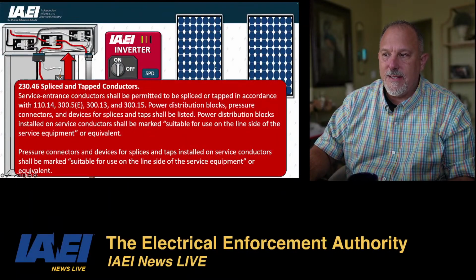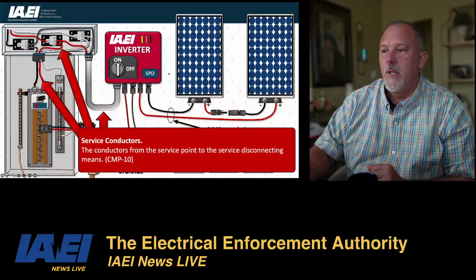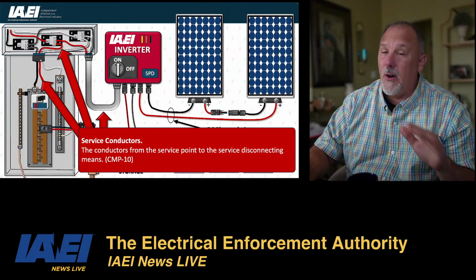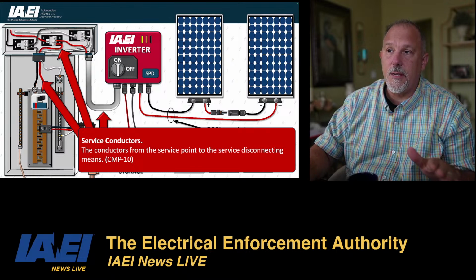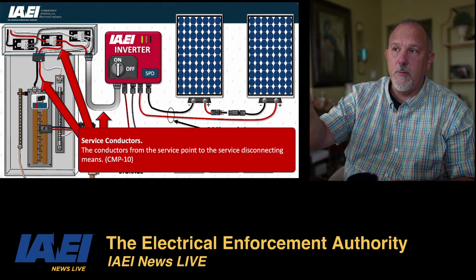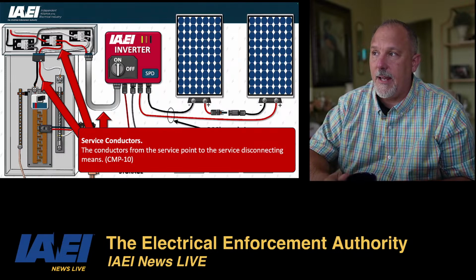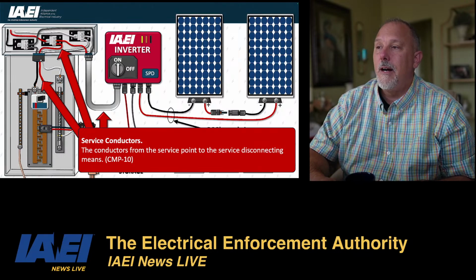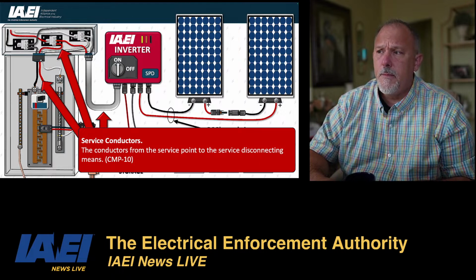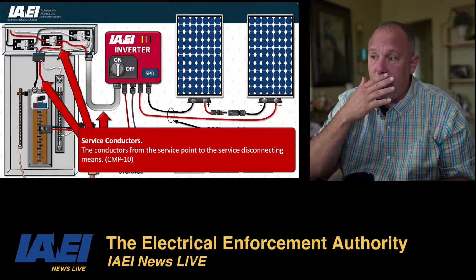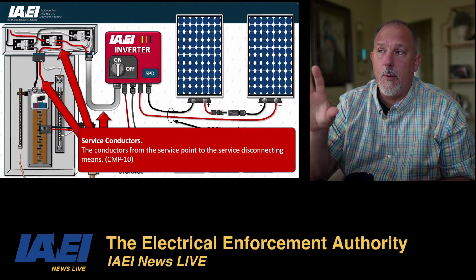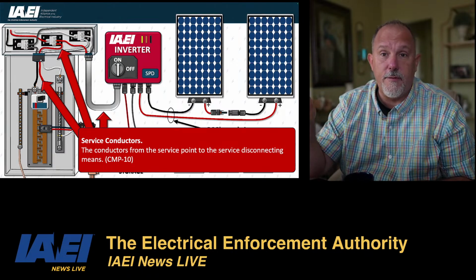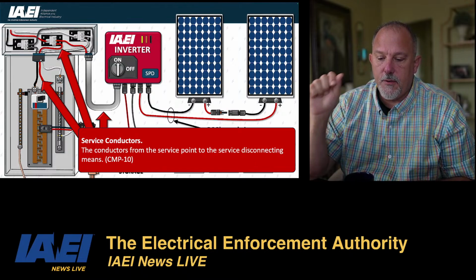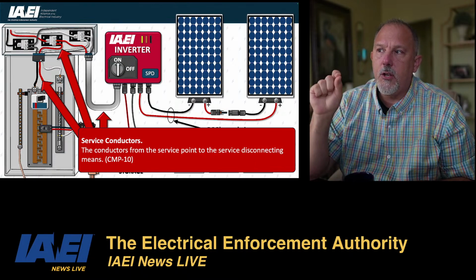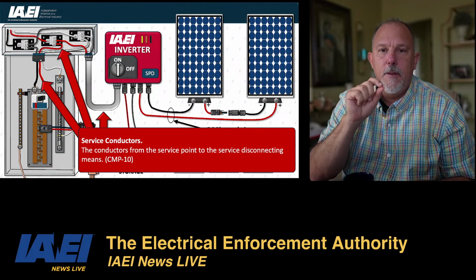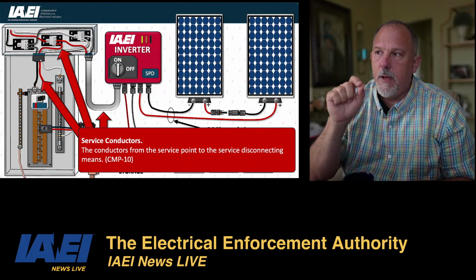There's your 230.46. We already talked about that. We already talked about the service conductors. Those are all service conductors. There's no difference between the conductors serving the panel board from that terminal block to the conductors serving the inverter. A big misconception I've seen is that a lot of people may not want to call those service conductors that go to that inverter.